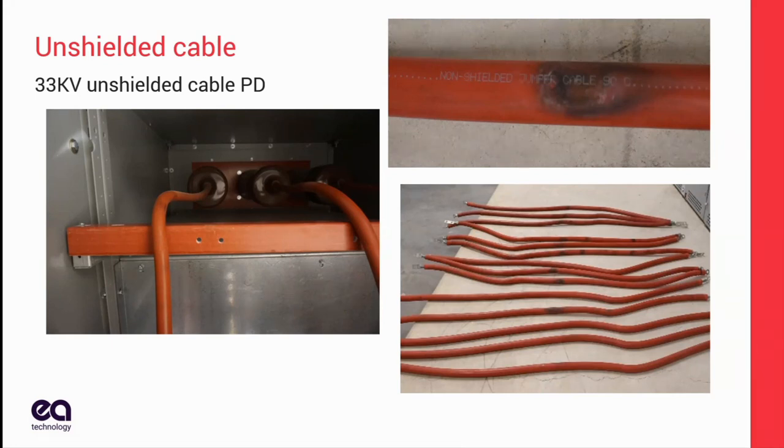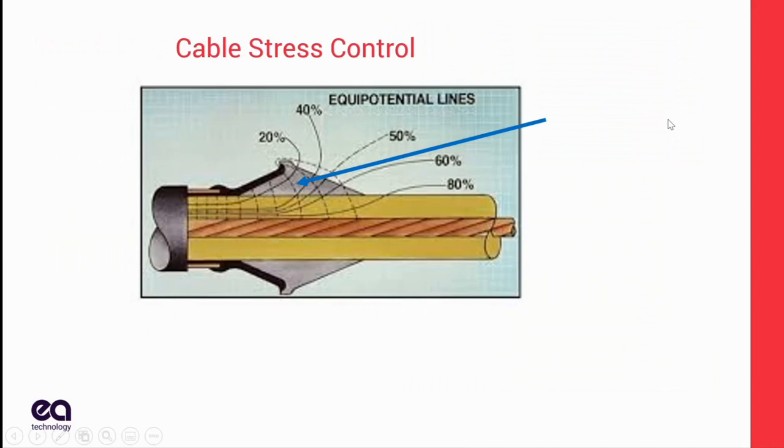This installation was approved by the switchgear manufacturer. That was the first person they called, and that was okay according to the switchgear manufacturer. So not everybody really understands the whole idea of field stress control.